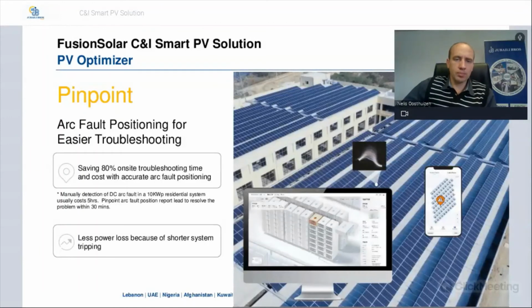Then with PV optimizers, we've got pinpoint accuracy. If you install the optimized solution and there's a fault on a module, it will specify the exact module that's at fault. It will tell you that it's string number 5, module number 10. So it saves you 80% of on-site troubleshooting time and cost through accurate arc fault positioning. Manual detection of a DC arc fault in a 10 kilowatt residential system usually costs 5 hours. A pinpoint arc fault position report leads to resolving the problem within 30 minutes. There is less power loss because of shorter system tripping. So these are just the advantages of using a fully optimized solution.